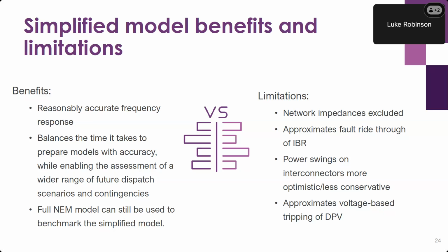But then we also have to be aware of any limitations. Because the model excludes actual network impedances aside from interconnectors, it can't accurately predict power system voltages throughout the network. It also provides an approximation of fault ride-through characteristics of IBR plant, and it provides an approximation of the voltage-based tripping behavior of DPV. But we can get around some of these things.